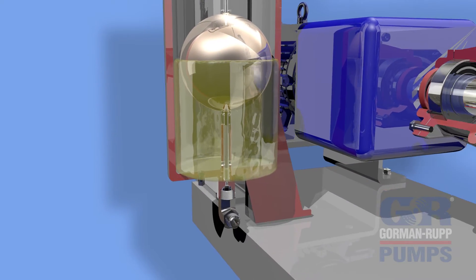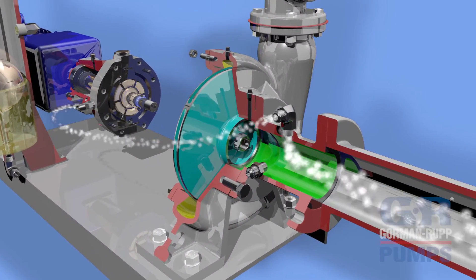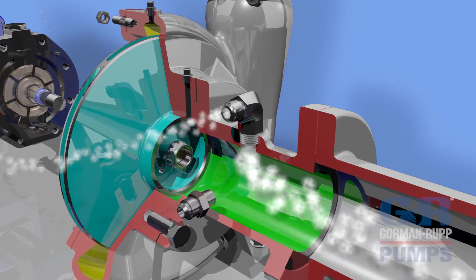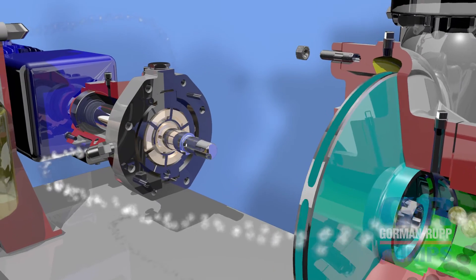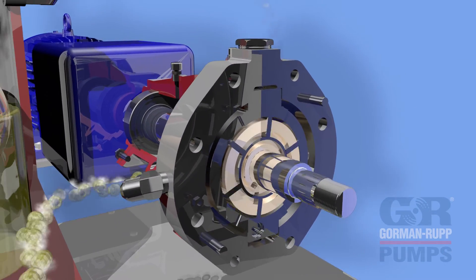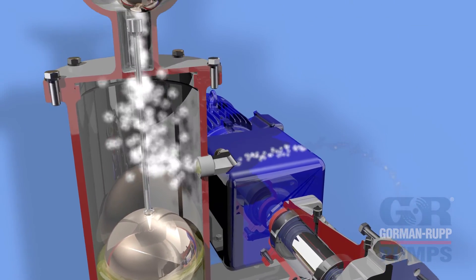The pump operation remains the same during the priming sequence, with the exception of air and vapor being routed to the priming pump from a priming tube on the suction inlet. For enhanced priming characteristics, priming through the impeller and body cover are not utilized in any BAR models. A discharge tube from the priming pump is routed to the air release valve, which allows air and vapor to be exhausted.